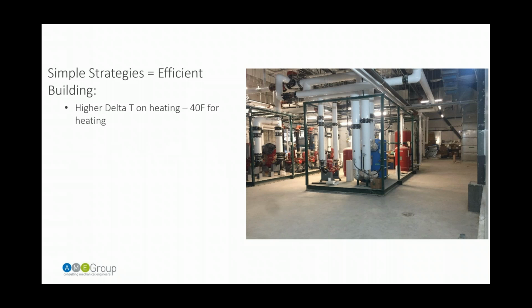And so for this building, because of the district energy connection, the heating system was relatively simple, so we went with a higher delta T on the heating system than what we might a lot of times when we're looking at heat recovery chillers providing part of that heat. And so a bigger delta T of 40 degrees Fahrenheit on the heating side of things. VFD obviously on pumps and fans, low velocity air handling systems. So we were actually able to get away with bigger air handlers and lower velocity and bypasses around our coils as well, just to try to reduce as much as we could the pressures through the air handlers.